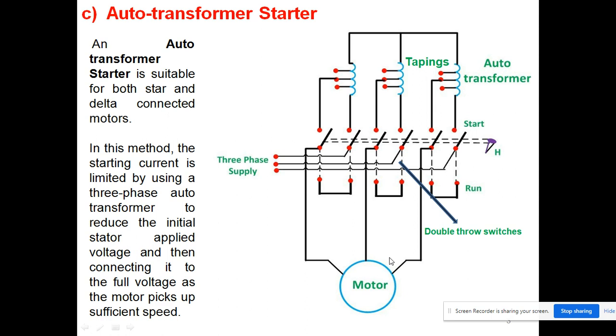What is basically happening in this method? You see here, there is a handle. These are double throw switches, and these double throw switches and this handle form the arrangement. At the starting, we put our handle position like this. It goes to the starting position. In this position, our power supply is connected to this auto transformer via this. Both of these are attached here. Then the second phase is connected to this auto transformer, and the third phase is connected to this one.